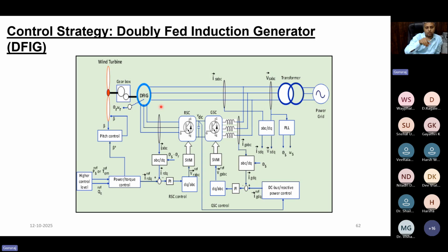For each particular turbine at a particular wind velocity, there is an ideal optimum speed that you want to track. If you track that speed, the whole job is done, you're tracking the MPPT. And how do you track the speed? By adjusting the current. How do you change the current? By changing the switching pulses of the rotor side converter, because the current output of this machine changes, since it's simple KCL. There is a current input also coming from the rotor side converter. You change this input, and the summed current also changes. That's how the rotor side converter helps us change the operating point and track the maximum power point. This is also a perturb and observe method.